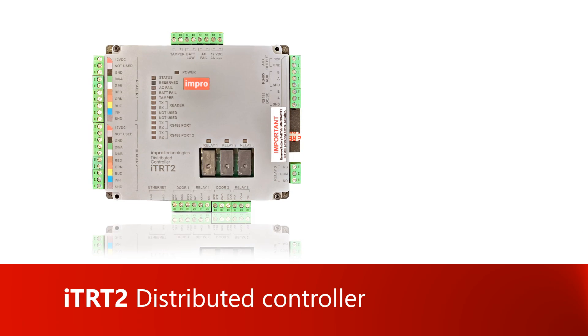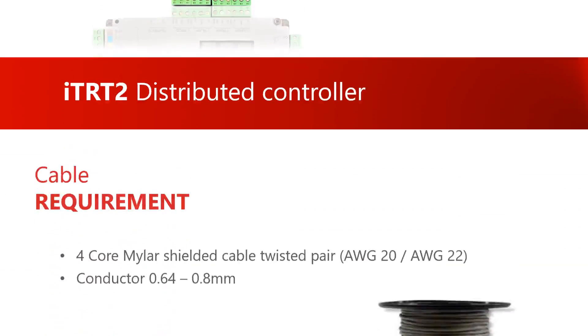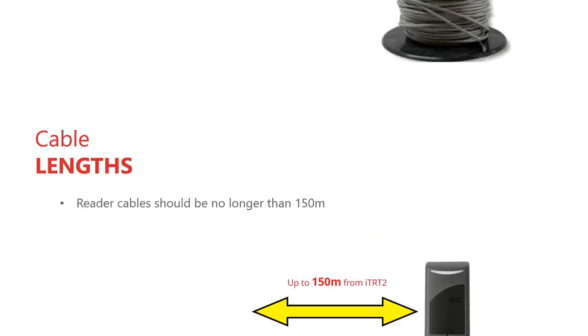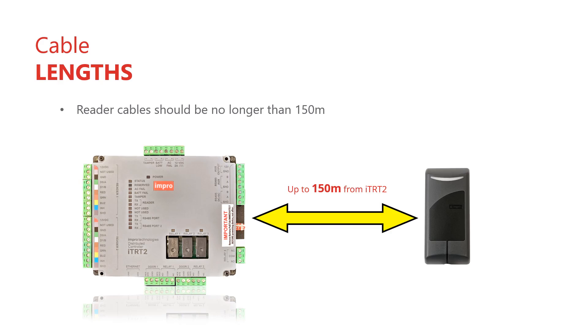Before we begin the wiring, there are some matters that must be borne in mind. You'll need screened two twisted pair Mylar cable with conductors no thinner than 22 AWG. Reader cable lengths may not exceed 150 meters.